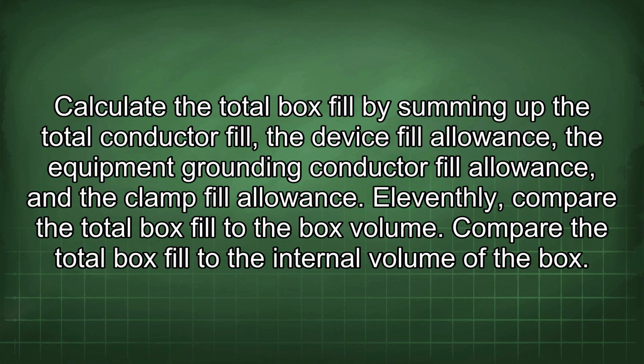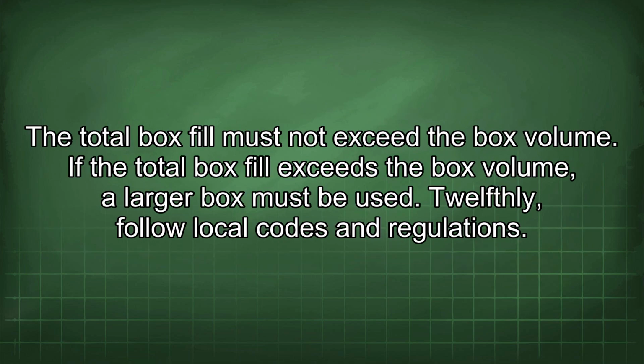Eleventhly, compare the total box fill to the box volume. Compare the total box fill to the internal volume of the box. The total box fill must not exceed the box volume. If the total box fill exceeds the box volume, a larger box must be used.